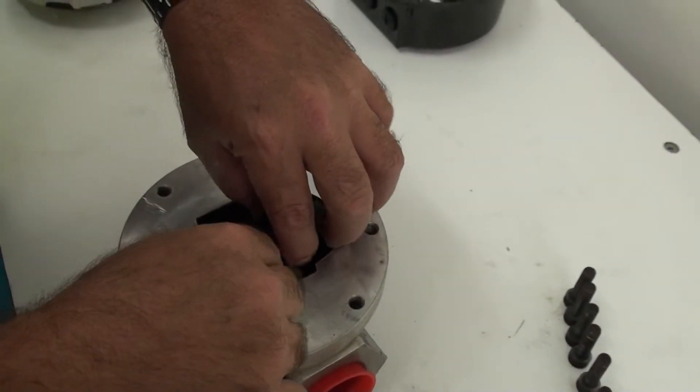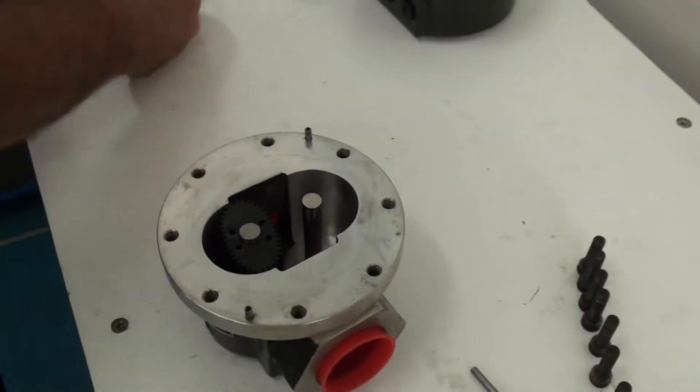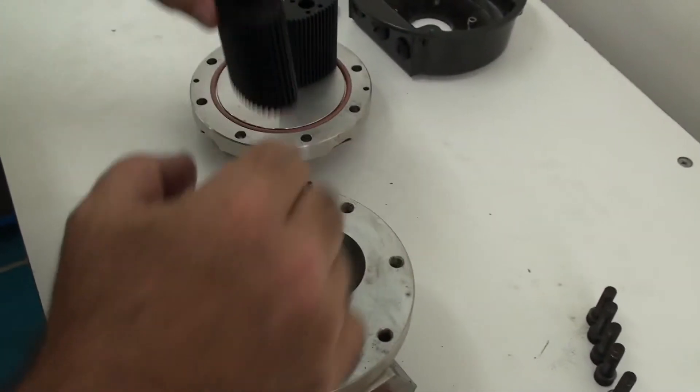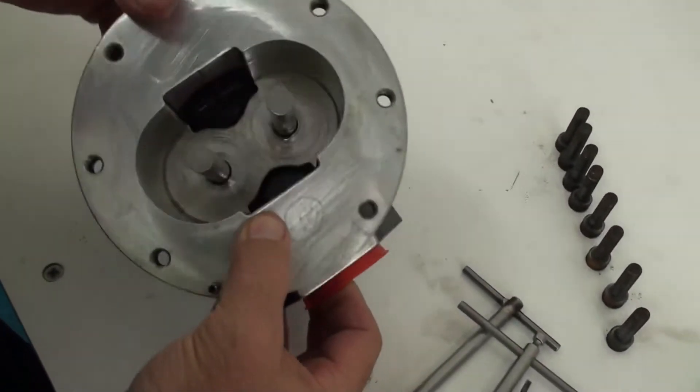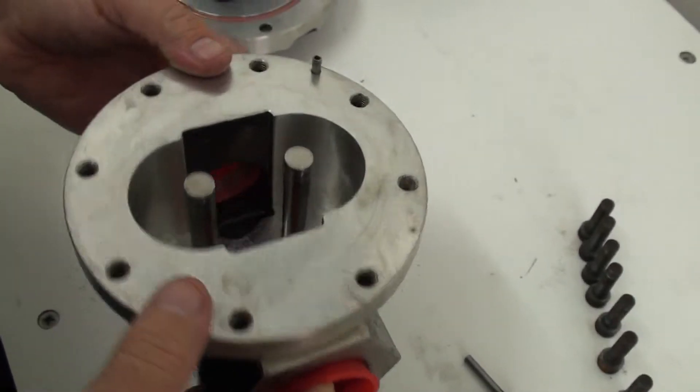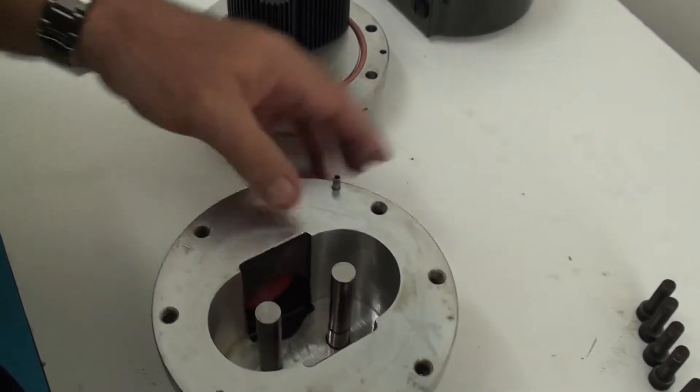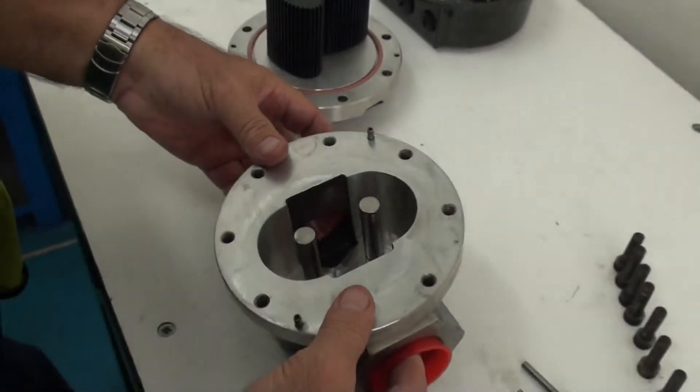What we need to do is remove the rotors out and taking note of the shaft that they fit on. So I'll put them back on the meter cap so that I know. And then we just do a general inspection of the meter body and make sure that there's no internal damage, there's no chunks out of it or nothing's happened to it and this one all looks fine.